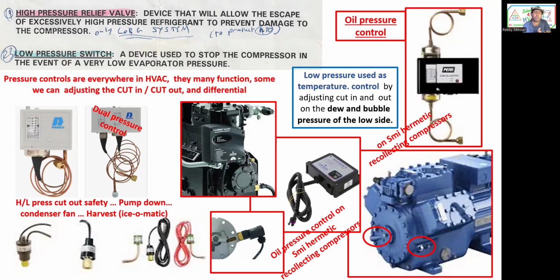It's very rare, but you have to know how to adjust it properly by adjusting the cut in and the cut out on the dew and the bubble of the low side pressure. I'll explain the dew and the bubble when I talk about the Freon and the chemistry going on between vapor and liquid, how some Freon will evaporate at a different rate than other Freon, depending if they are mixed or not. And to find out the bubble of the low side, because bubble is on the high side, you actually have to look at a different PT chart than the one we have. I'll explain all this when I do the refrigerant class, how to adjust the pressure control and step control in refrigeration. But it's rare to do that, very rare. I only did it 4 or 5 times in my life.